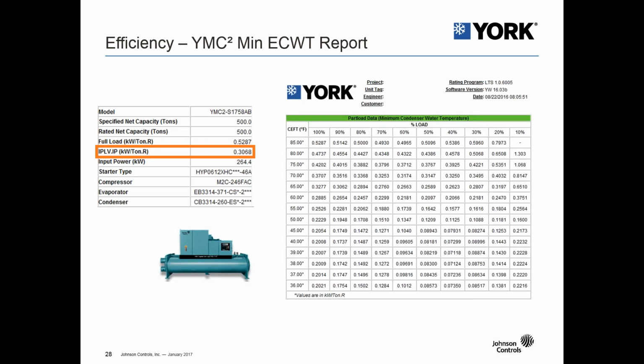And then when you look at the minimum entering condenser water temperature report, you can start to see the full operating range or the full map of the chiller. So down the left-hand side, you'll see entering condenser water temperatures starting up at the design point at 85, and then it increments down all the way to 36 degrees entering condenser water temperature. And across the top, you'll see the load going from 100% or 500 tons all the way down to 10% load.